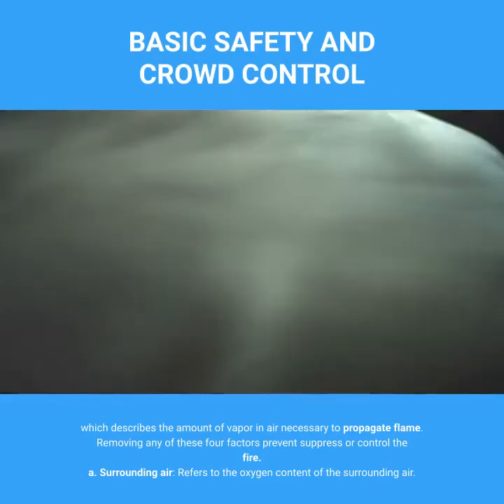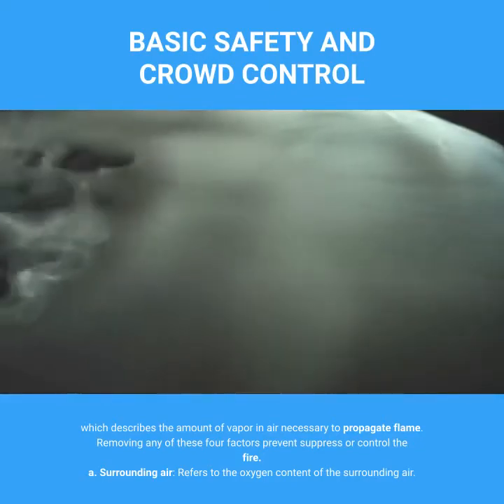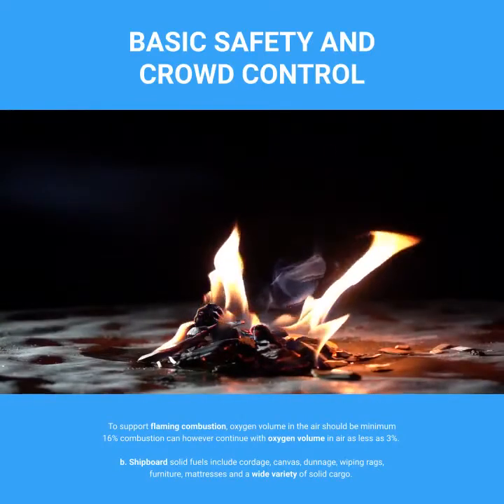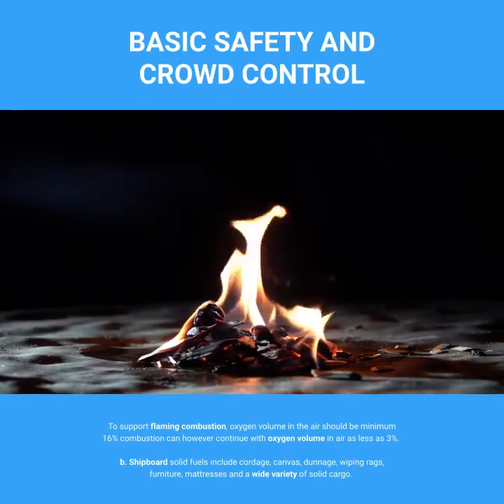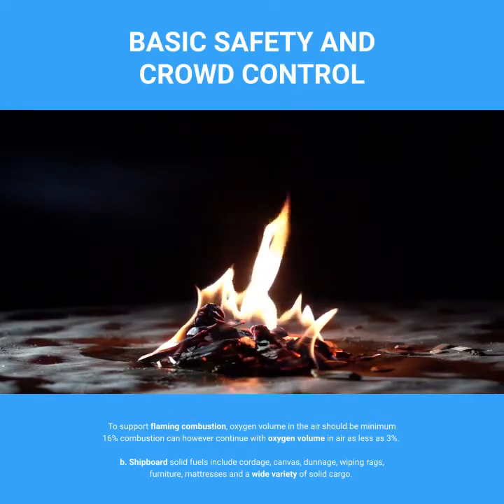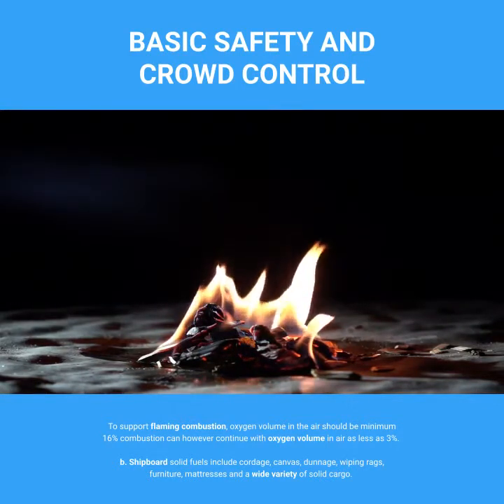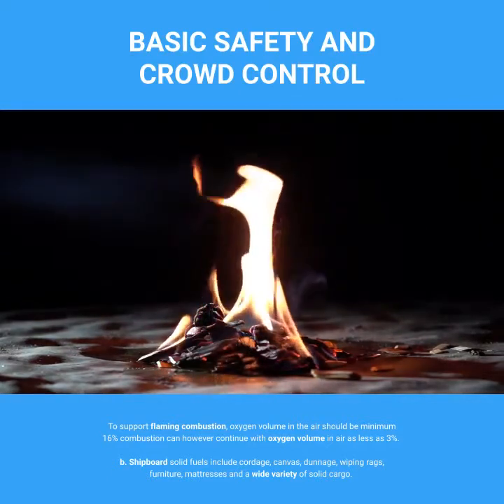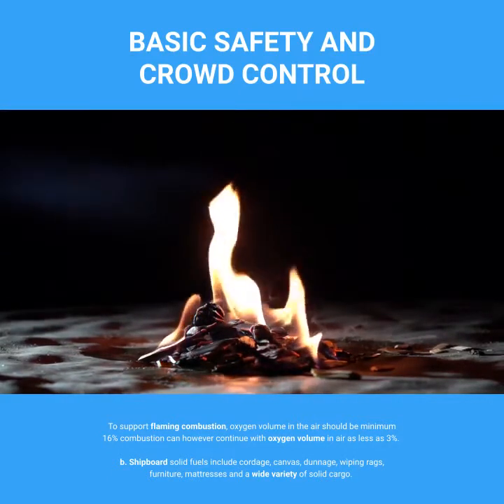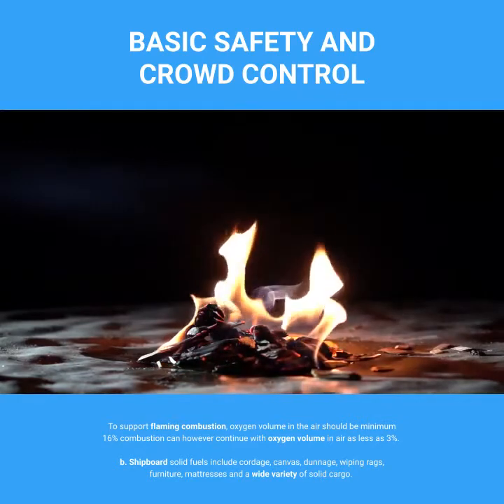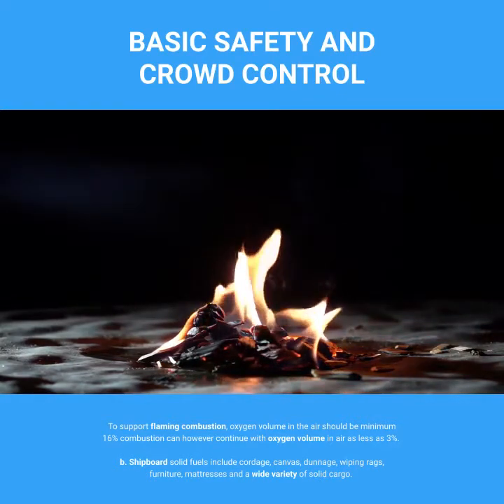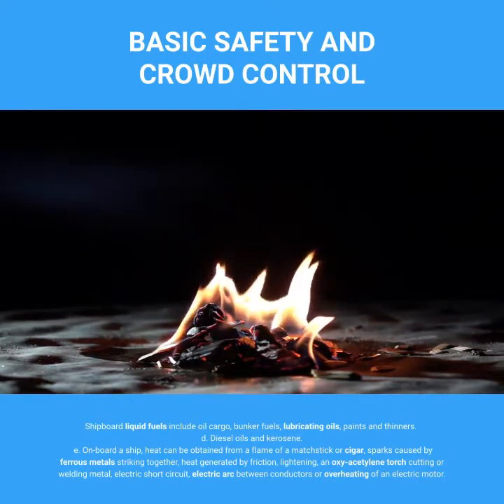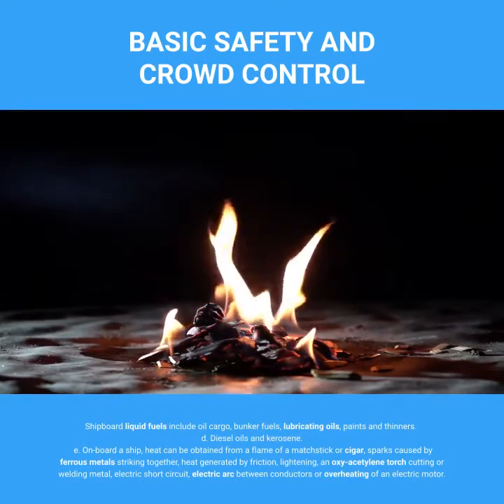Surrounding air refers to the oxygen content of the surrounding air. To support flaming combustion, oxygen volume in the air should be a minimum of 16%; combustion can however continue with oxygen volume in air as low as 3%. Shipboard solid fuels include cordage, canvas, dunnage, wiping rags, furniture, mattresses, and a wide variety of solid cargo. Shipboard liquid fuels include oil cargo, bunker fuels, lubricating oils, paints and thinners.